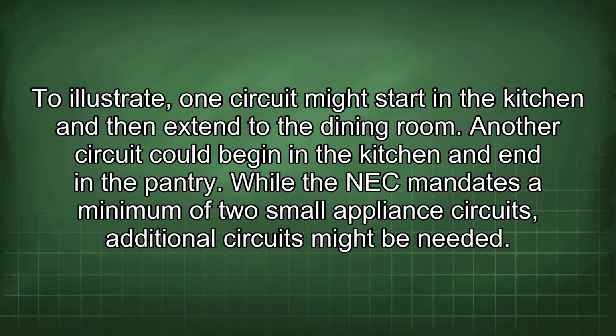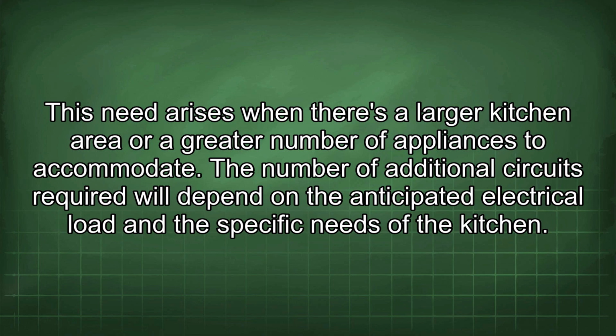While the NEC mandates a minimum of 2 small appliance circuits, additional circuits might be needed. This need arises when there's a larger kitchen area or a greater number of appliances to accommodate. The number of additional circuits required will depend on the anticipated electrical load and the specific needs of the kitchen.